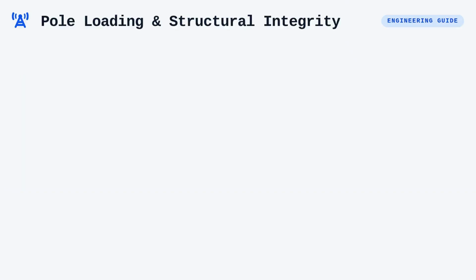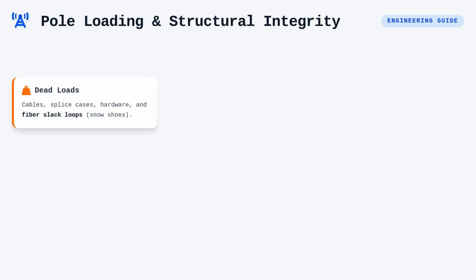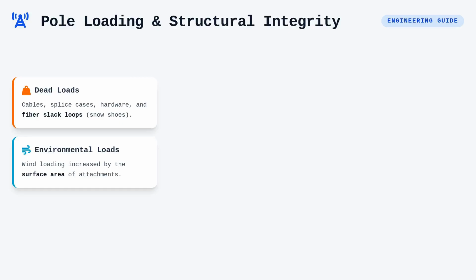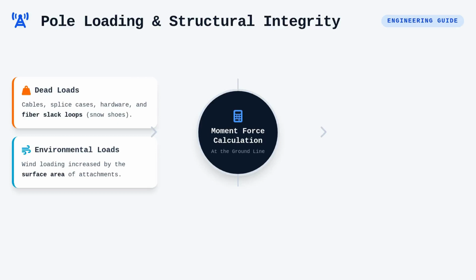Structural integrity relies heavily on the pole loading analysis, which is the process of calculating the combined stress exerted by all attachments on a utility pole. Every cable, splice case, and hardware component introduces a load that must be accounted for against the pole's inherent breaking strength. When we add fiber slack loops, often managed by snowshoes, we are adding both dead weight and surface area for wind loading, necessitating a recalculation of the moment force at the ground line.